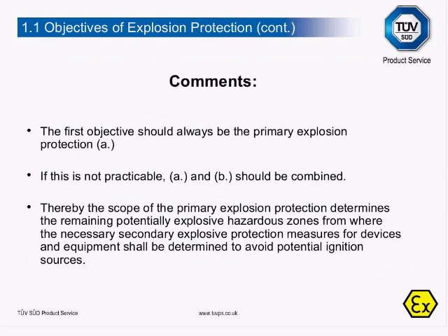The first objective should always be Primary Explosion Protection. If this is not practicable, A and B should be combined. The scope of Primary Explosion Protection determines the remaining potential explosive hazardous zones, from where the necessary secondary explosion protection measures for devices and equipment shall be determined to avoid potential ignition sources.